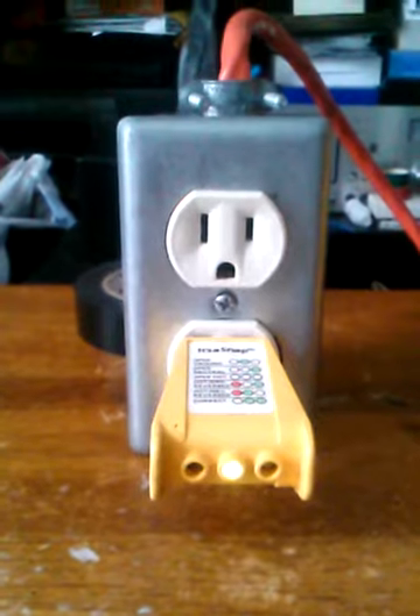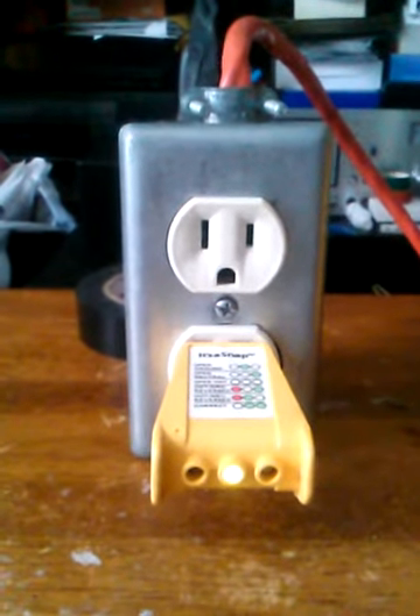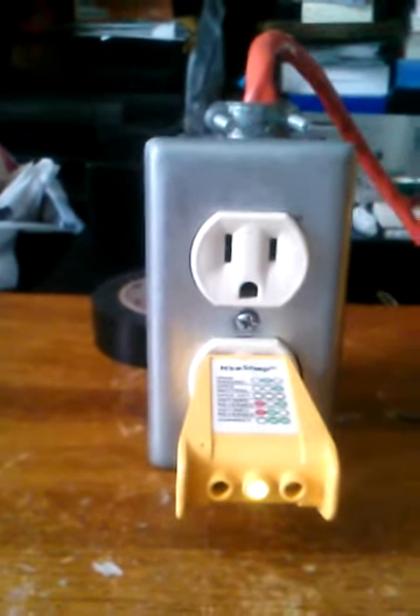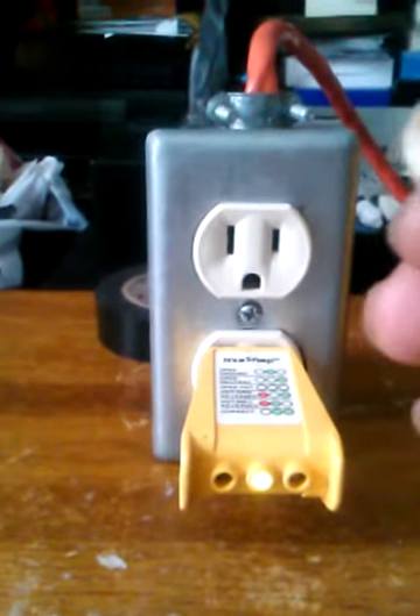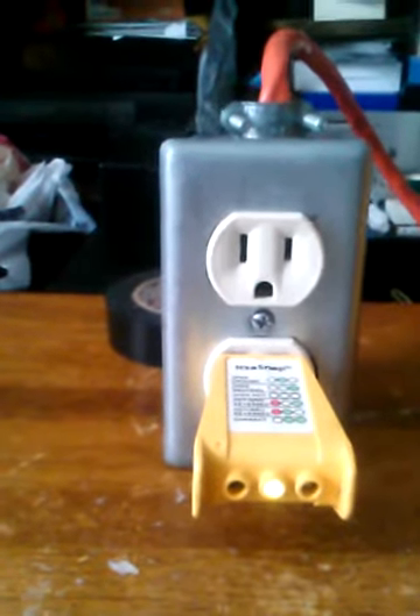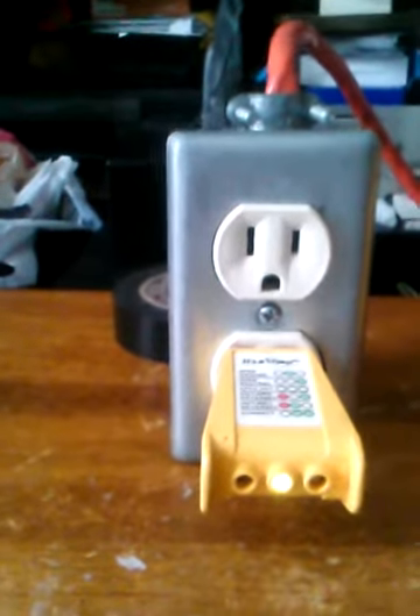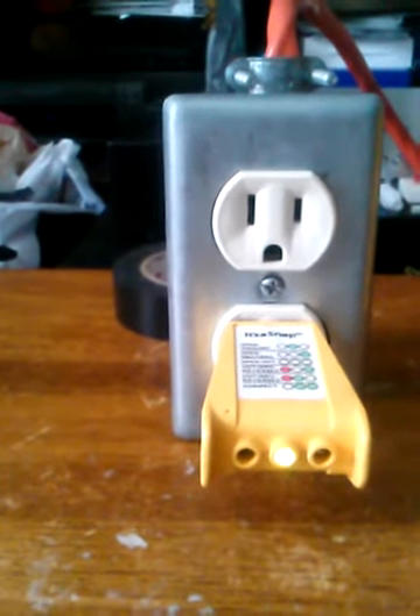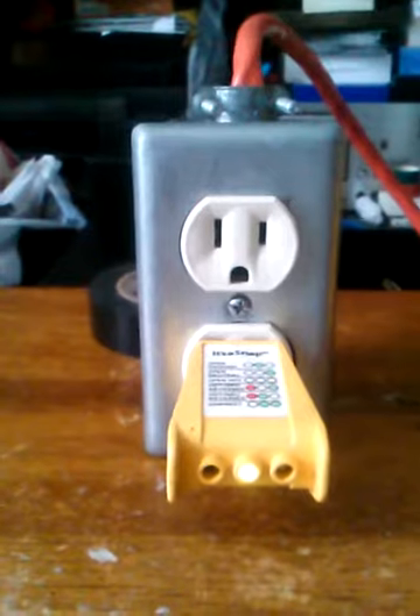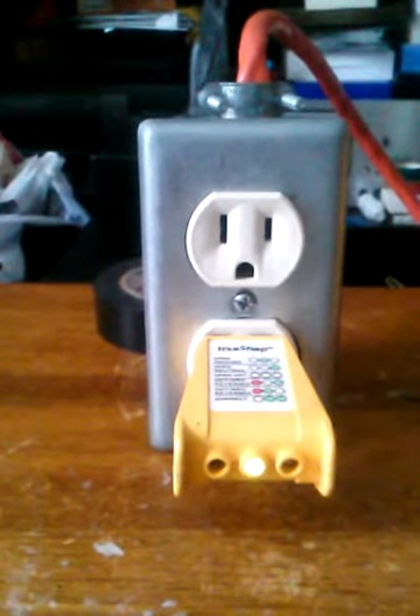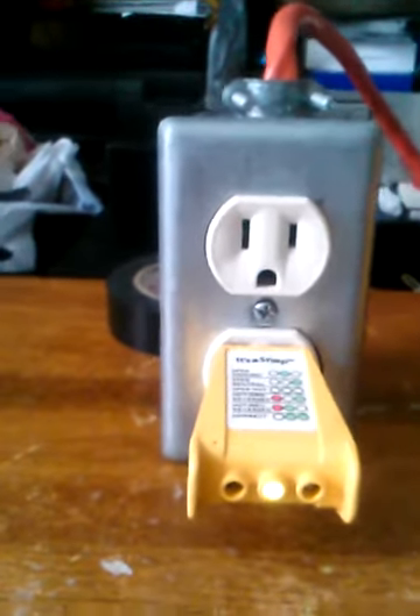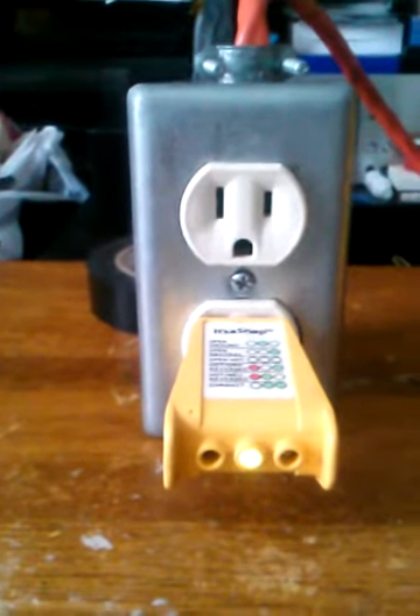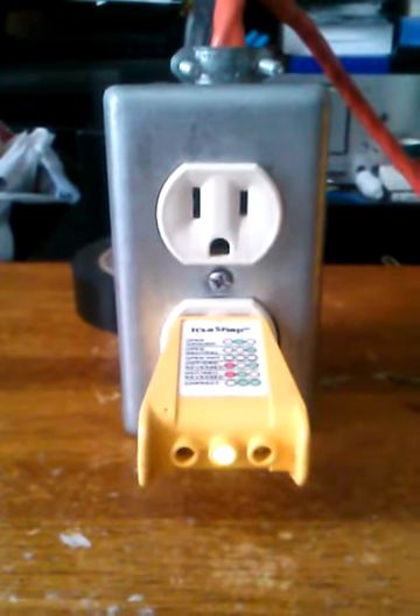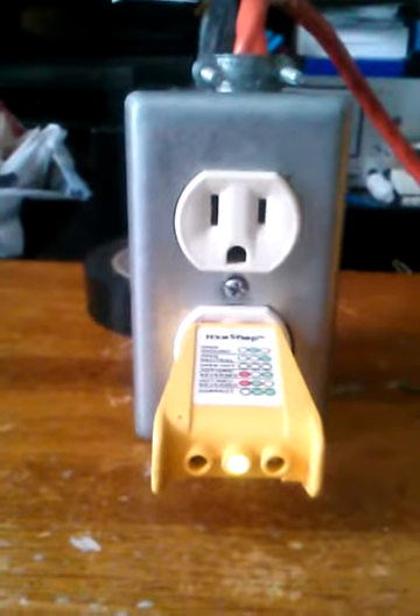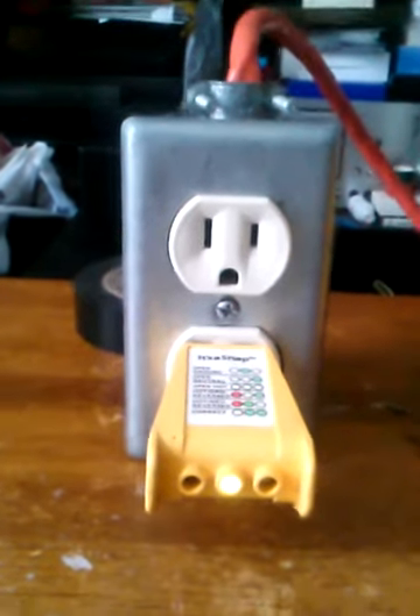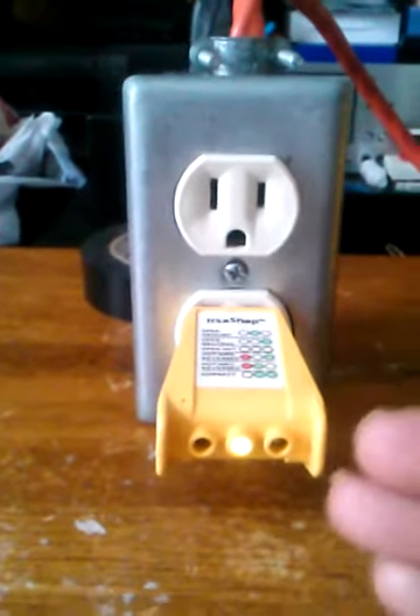So AC or armor clad wiring, which is the old BX tubing. Some may have the little ground sheathing that you just wrap around it to use it for continuity purposes, but some don't have that little thin wire that you wrap around the steel or armor clad mesh, which acts as a ground. But if you don't, and for some reason it won't ground, most likely the old BX or the old armor clad is rusted, and you may have a receptacle in this case.